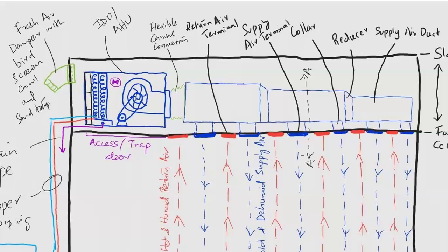So the plenum area is always considered a negative area. Why? Because the return air which comes from those rooms passes across that area round and round. So later, due to the suction of this fan, if a fan is working, at the backside of the fan you can feel some kind of suction. So due to this negative pressure on the backside of this machine, the return air is drawn along the right-hand side to the indoor unit itself. And yesterday I mentioned the fresh air connection, isn't it? So typically on the same plenum area walls, they will provide some wall openings. And sometimes this wall opening is fitted with a fresh air duct or a fresh air duct damper. The purpose of this fresh air damper or fresh air duct is to provide atmospheric air to the plenum area itself, not to the air conditioned room.